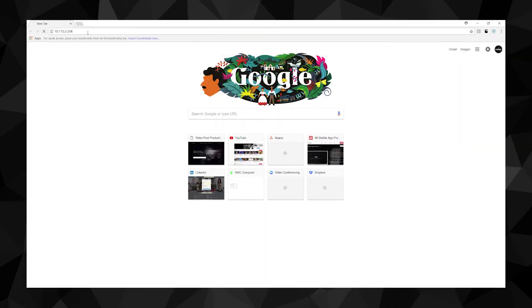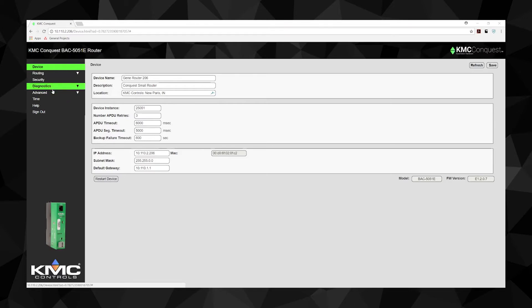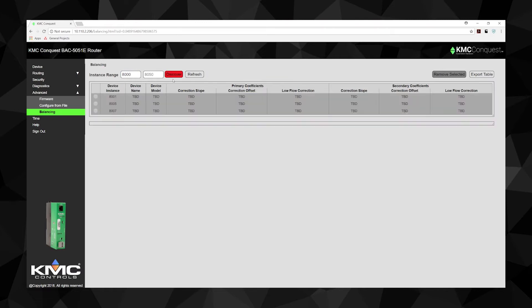Type the router's IP address into a web browser and login. You will find the balancing feature under the Advanced tab on the left-hand menu. Begin by entering the range of device instance values for the VAV units you are balancing. Click Discover. This will create a list of up to 50 devices.